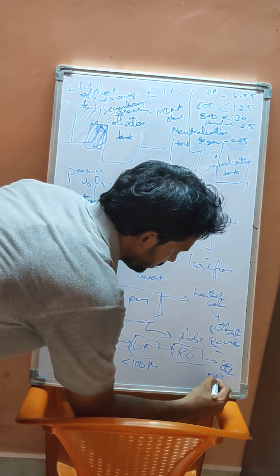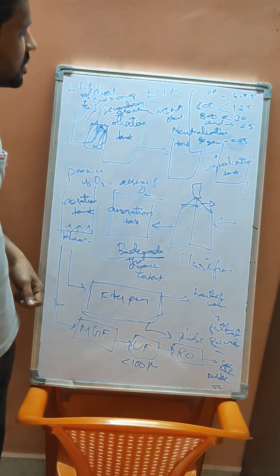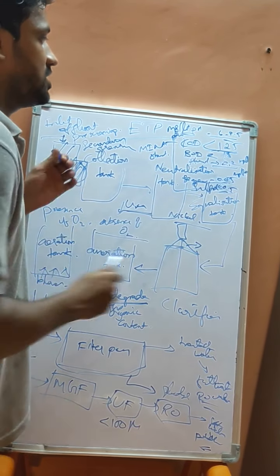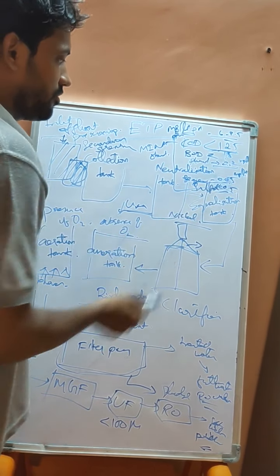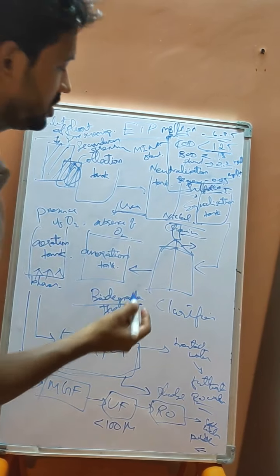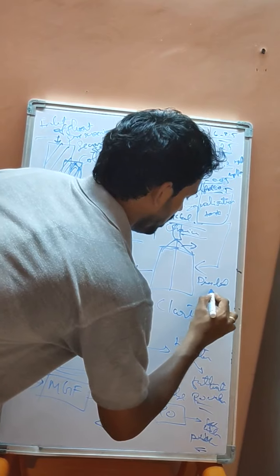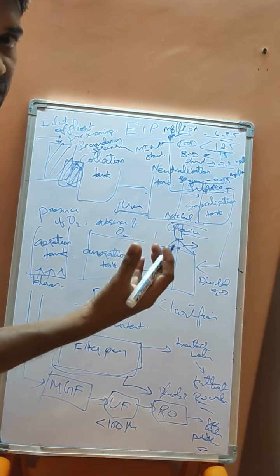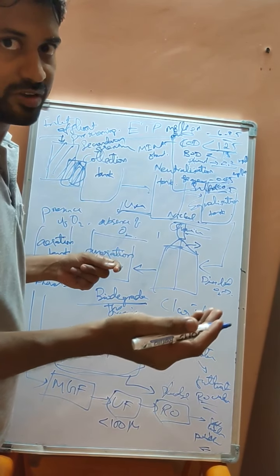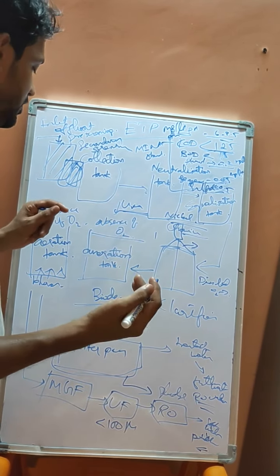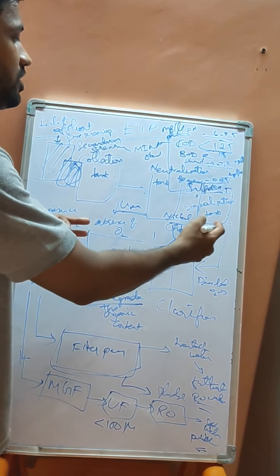The output after RO is used as soft water or for potable use. Key disposal parameters to note: COD should be less than 125, BOD should be less than 30, phenol is 0.2 mg/L, and certain heavy metals like nickel, chromium, and sulfide also have specified limits. Dissolved oxygen and conductivity are also measured — conductivity is especially important for DM water preparation. For solid-based effluent plants, the process can stop after equalization without needing all further steps.